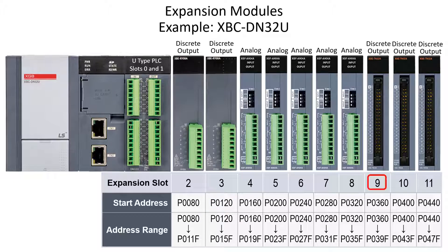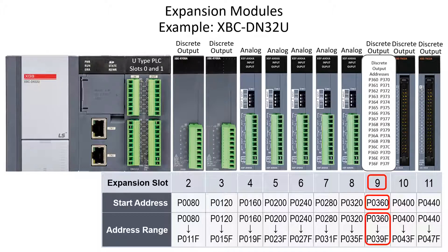A 32-point digital output module is configured in slot 9. The starting address is P word 36 bit 0 and the range is P 36 0 through P 39 F. The 32 output points are addressed P 36 0 through P 37 F. Though every expansion module slot is allocated 64 bits, the physical addresses in each slot are dependent on the I/O count of the discrete module.